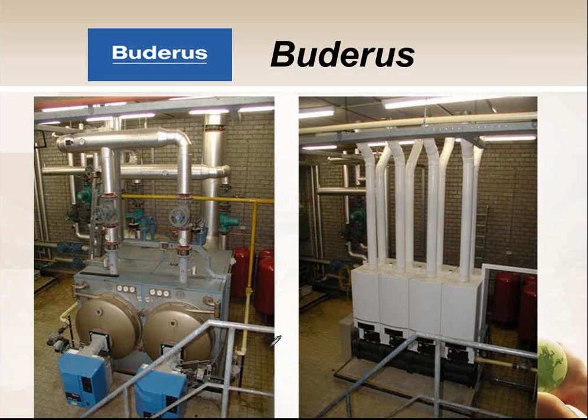So instead of having to clean the water out of the boiler, the water's only going to be there briefly. It's not like an old cast iron or even a newer aluminum block boiler where the water can sit down at the bottom and debris can accumulate. This is all inside a tube, so it moves pretty quickly through there. So strainer on the water side, clean that out, and then clean out the combustion air side pretty good.